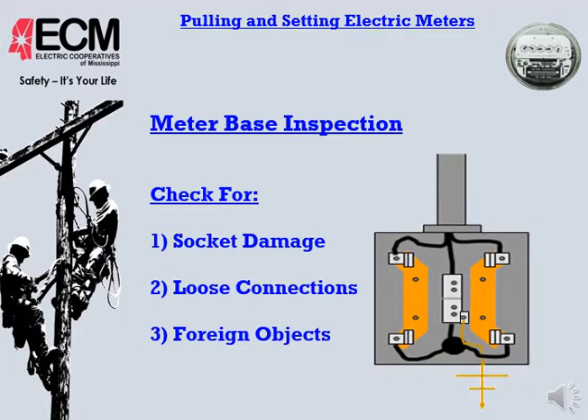Meter base inspection, of course, is very important. We're going to be looking for socket damage. Socket damage can be caused from a lot of different things. These meter bases are out there for an extended amount of time. Trees could fall, pull meter bases off of the house, off of the building. A lot of cases, these meter bases are out there for an extended amount of time, the covers are removed and vandalized. People steal parts out of the meter bases for their own use.